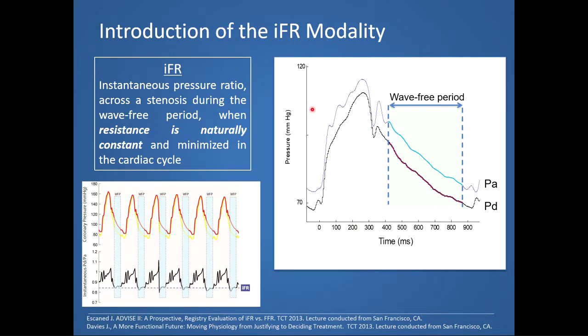This introduced the idea of IFR — the instantaneous wave-free ratio — the instantaneous pressure ratio across the stenosis during the wave-free period when resistance is naturally constant and minimized in the cardiac cycle. The wave-free period starts at 25% of diastole after the dicrotic notch and ends 5 milliseconds before the upstroke in aortic pressure. Importantly, the IFR measurement is stable during this wave-free period at any instantaneous point within this period.